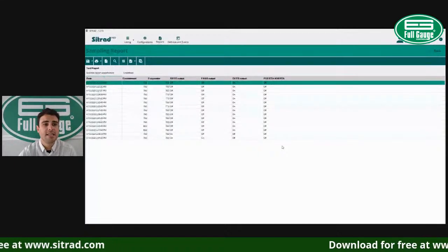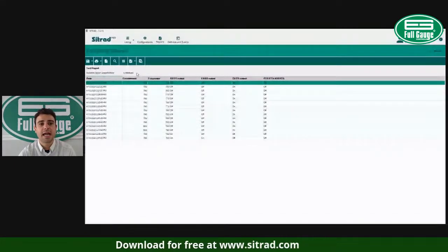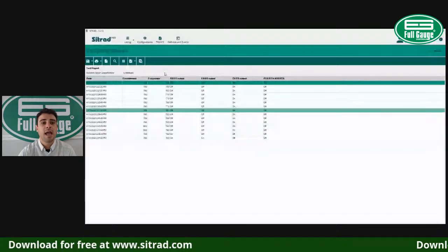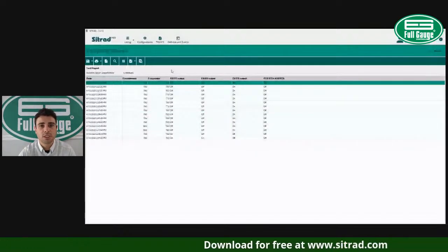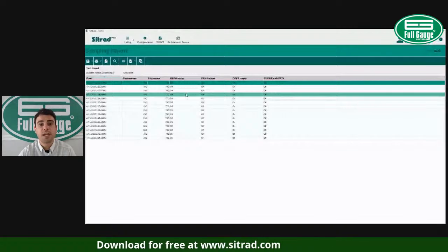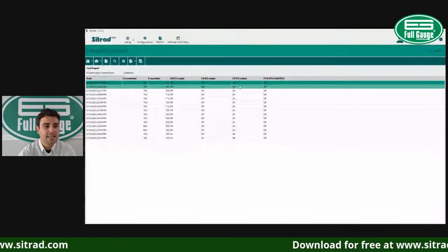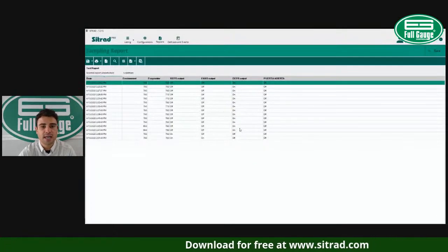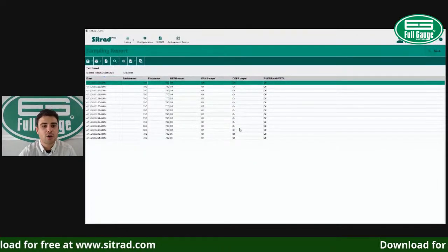And now we can see what was the room temp, the box temperature, and the coil temperature during that report period. And also whenever my compressor was on, here we can see that the compressor was off, because there was a defrost cycle on. And during the last 10 minutes, our defrost cycle went off and the compressor went on.